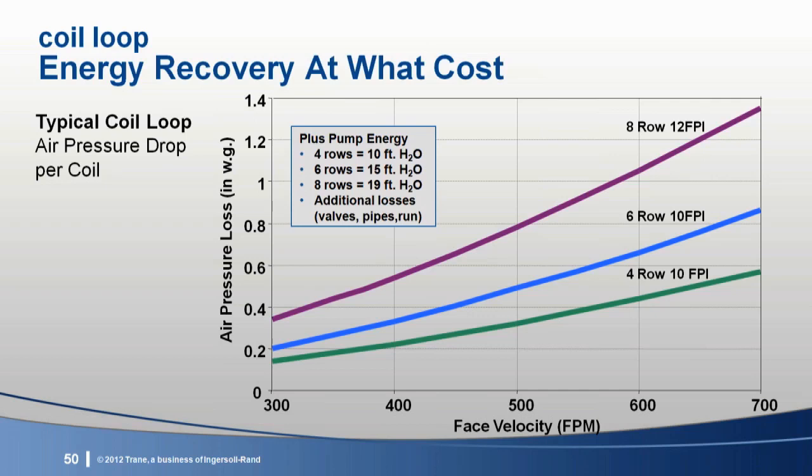Note that coil loops are flexible, however the coils are not mounted directly in the ductwork, where air velocity could be 4 times higher than shown. The coil needs to be mounted with drain pans as condensate is possible, access for cleaning, and a pre-filter is required to keep clean. This air handler may or may not have a fan, as it may be ducted up to a rooftop unit or some other equipment that includes a fan sized to handle this extra pressure loss.